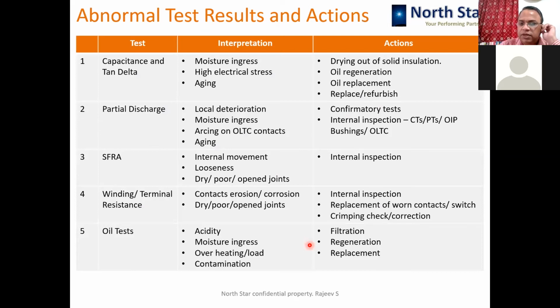So what happens when we get some abnormal test results? I have put some of the tests over here, not all of the tests. For example, if you get capacitance and tan delta test results abnormal, meaning you are getting high tan delta, the reason could be high moisture ingress, or high electrical stress, or aging. Or partial discharge also will give you tan delta value deterioration. So actions could be drying out of the solid insulation, oil regeneration, oil replacement, or replace or refurbish the oil.